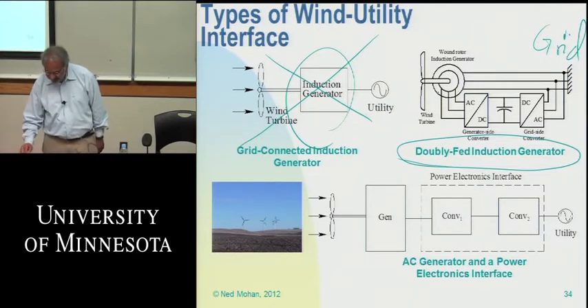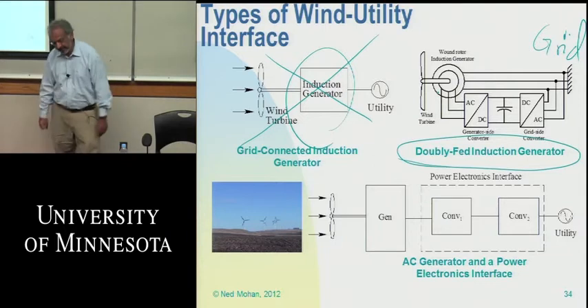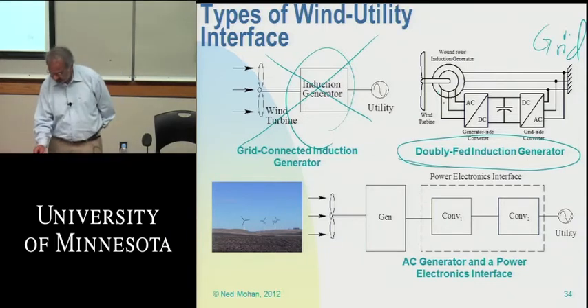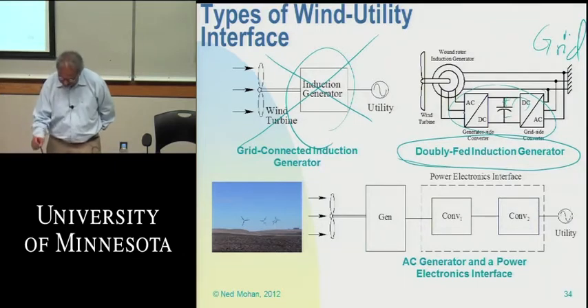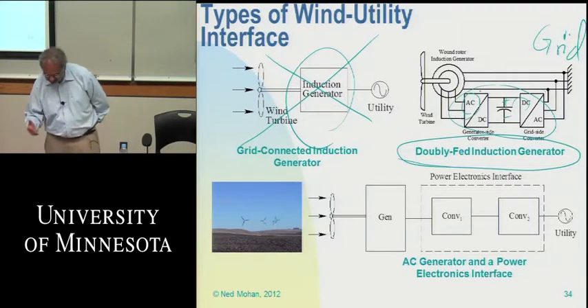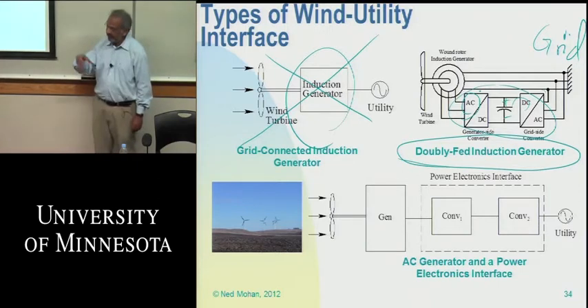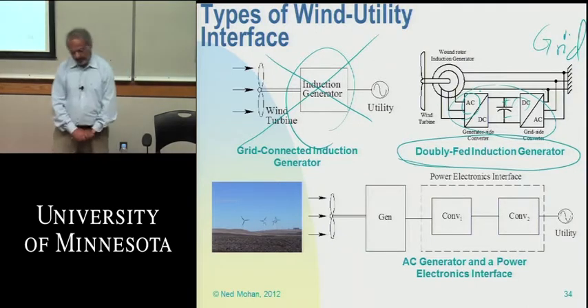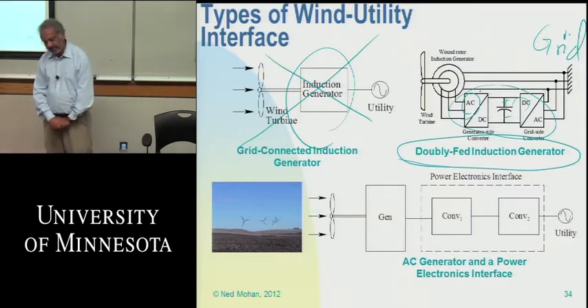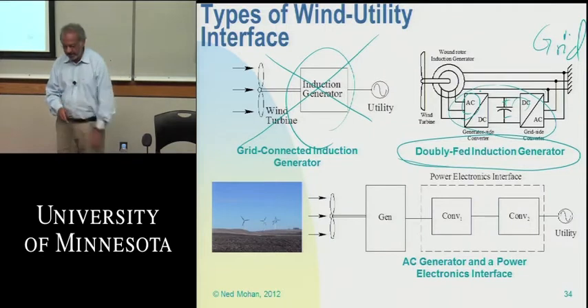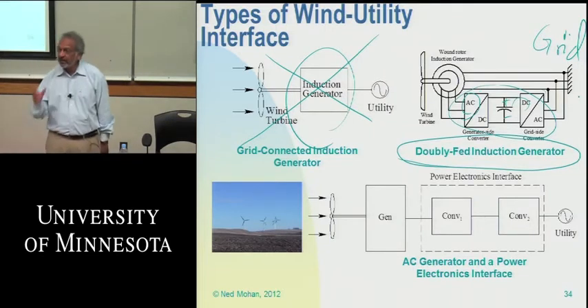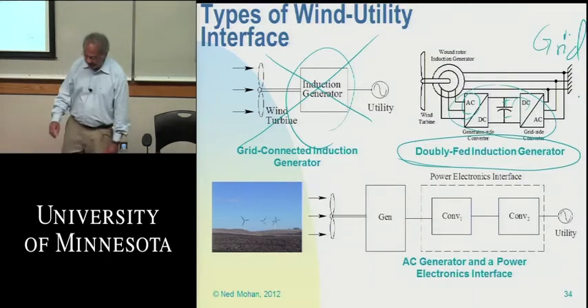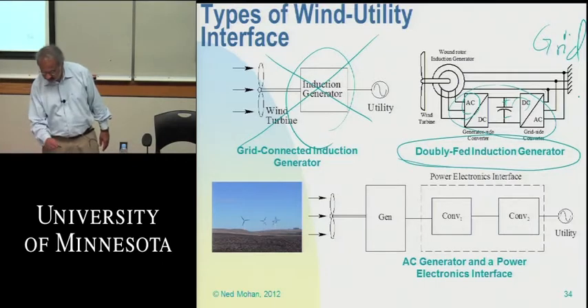But the rotor is a wound rotor machine, and you inject currents into the rotor through this power electronics arrangement over here. So you have AC on the grid side, you convert into DC across this capacitor, and from this DC, by chopping it up, you produce a low frequency AC and you supply currents through slip rings and brushes into this rotor. Okay, and so this is a doubly fed machine, and quite often used. And the advantage here is that most of the power that is generated flows directly from the stator to the grid without any power electronics. Whereas only, let's say, 10 or 15 or 20% flows through the rotor circuit.